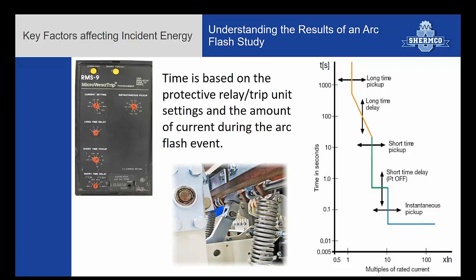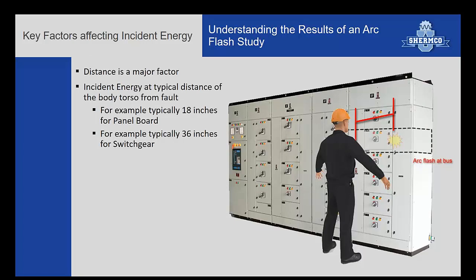And then, how much current is there when the event's happening? We're typically going by arcing current, not by short circuit current. And we're going to talk a little bit about the differences between arcing and short circuit current. But how much current is there depends on how quick you get into the curve of the breaker. So settings are very important. Another key factor is distance. How close the worker is to where the event's happening is a major factor in how much exposure there is to their body.